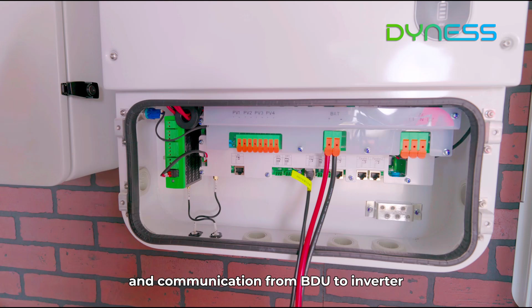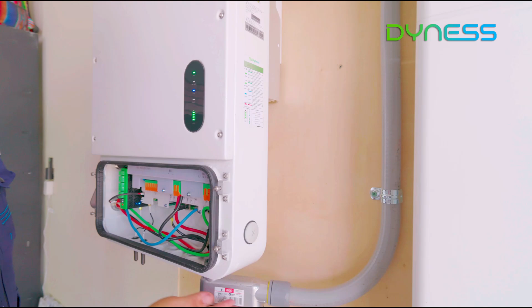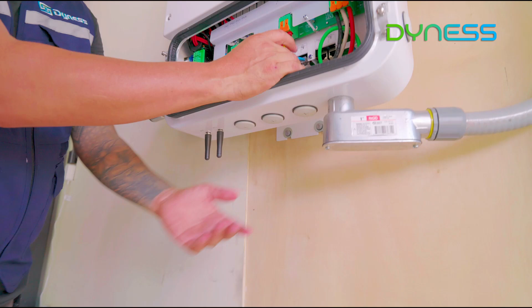So when installing the BDU conduit, you can use personal preference as long as it meets the NEC code. Once you're leaving the BDU, you come down the way we did it in the installation here. We brought it underneath, and why we brought it underneath is for future expansion. This gland is open. You can still use it, but in this case what we did was we brought it in here, up, over. So these two wires, the positive and negative, as well as the BMS communication wire from BDU to inverter, is protected at all times. That's for the purpose and the greatness that Dyness has this pre-cut out 1-inch knockout on the bottom and 1 inch on the side.